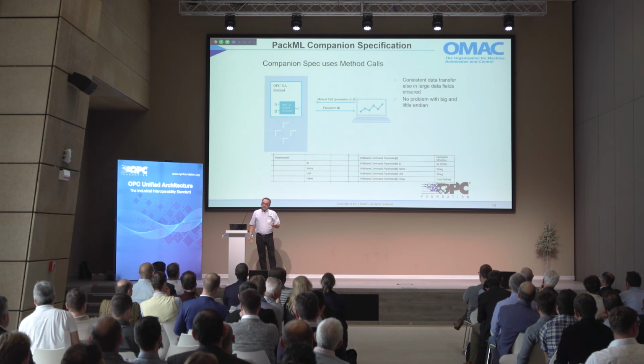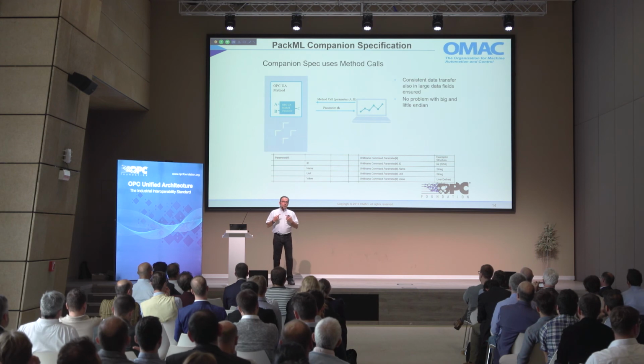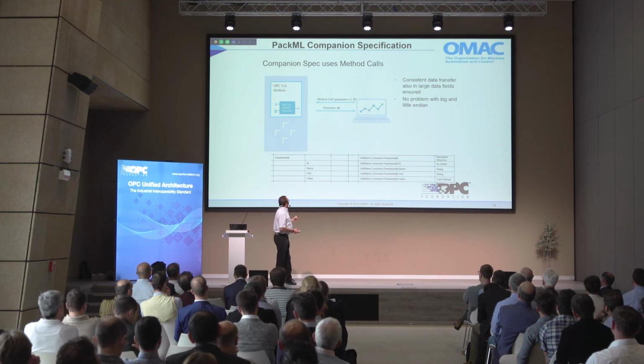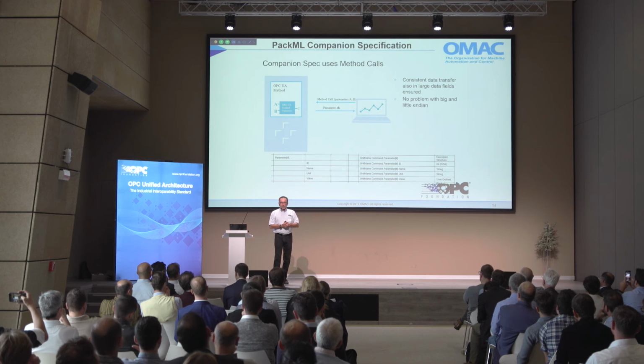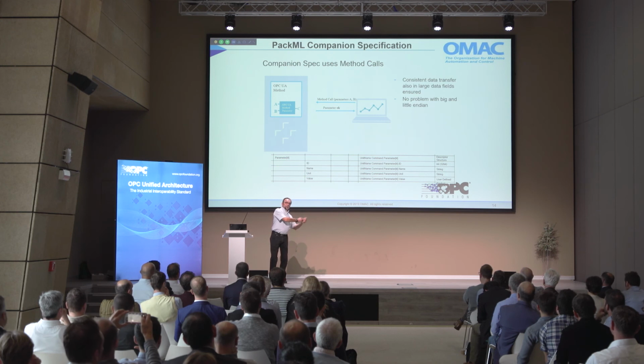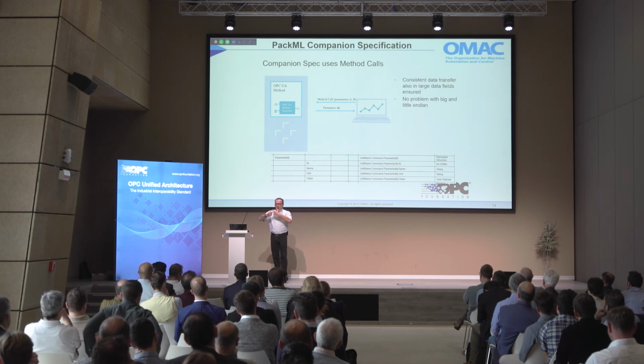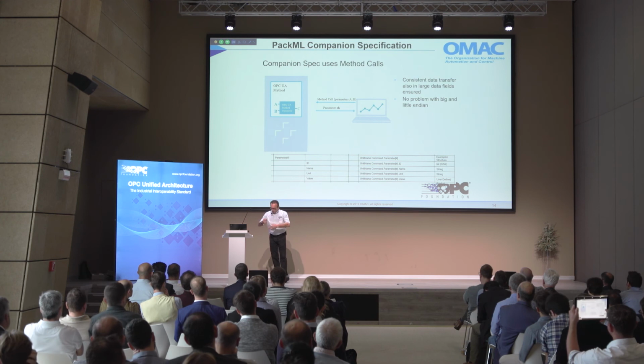Yeah, and there we said, okay, all those data transfers which we know, we will do as OPC UA method calls. A method call is something the application can collect and send consistently to the application program. The application program knows, oh, hello, here is a method call. Take all the values there, operate with them, and send us a result back, okay, or I don't know, wrong. But this is really consistent on both sides.